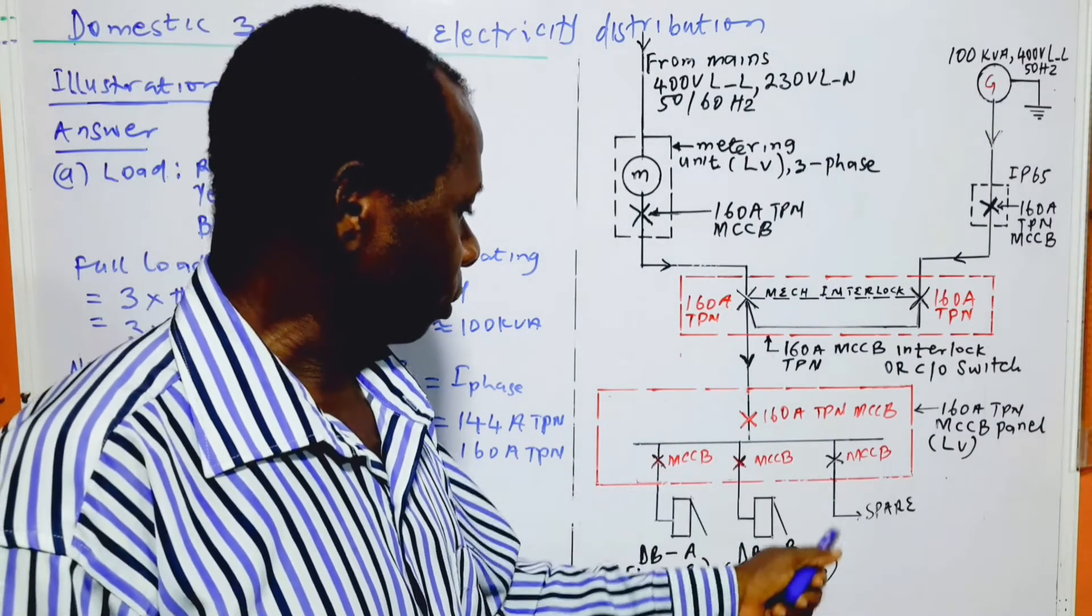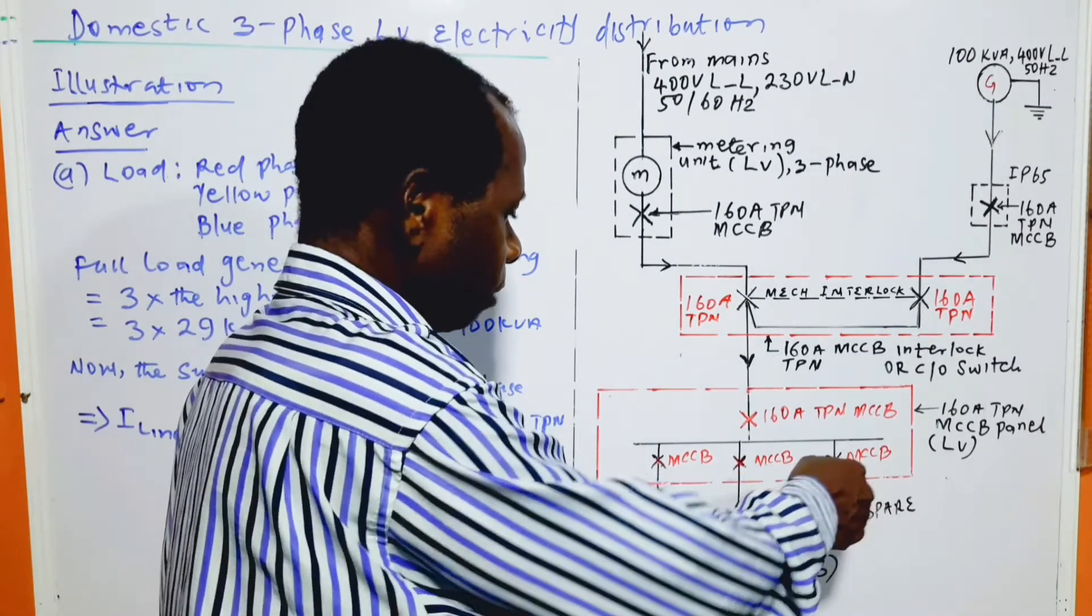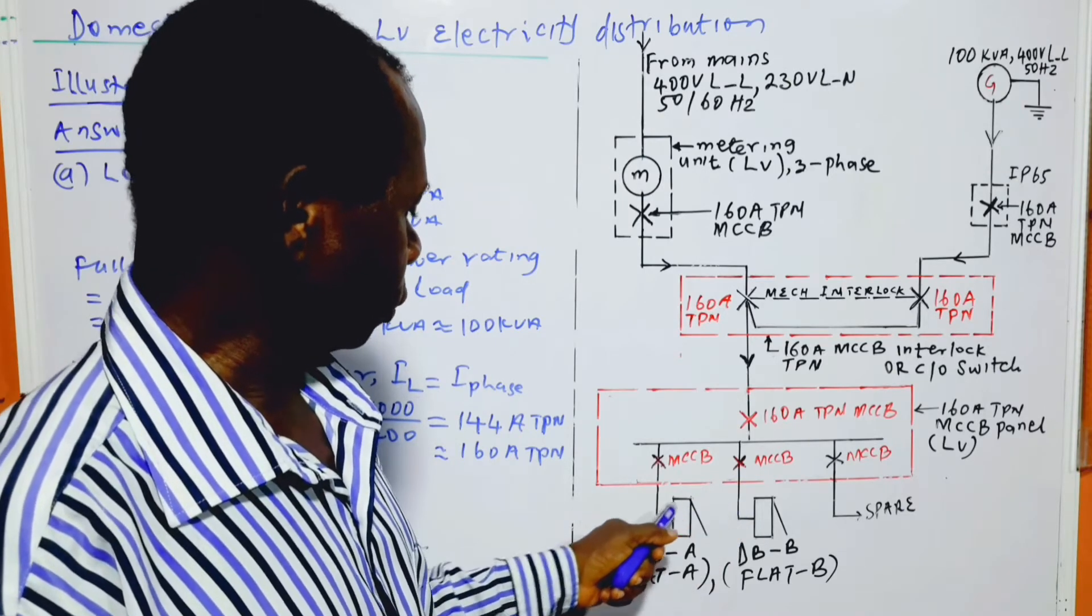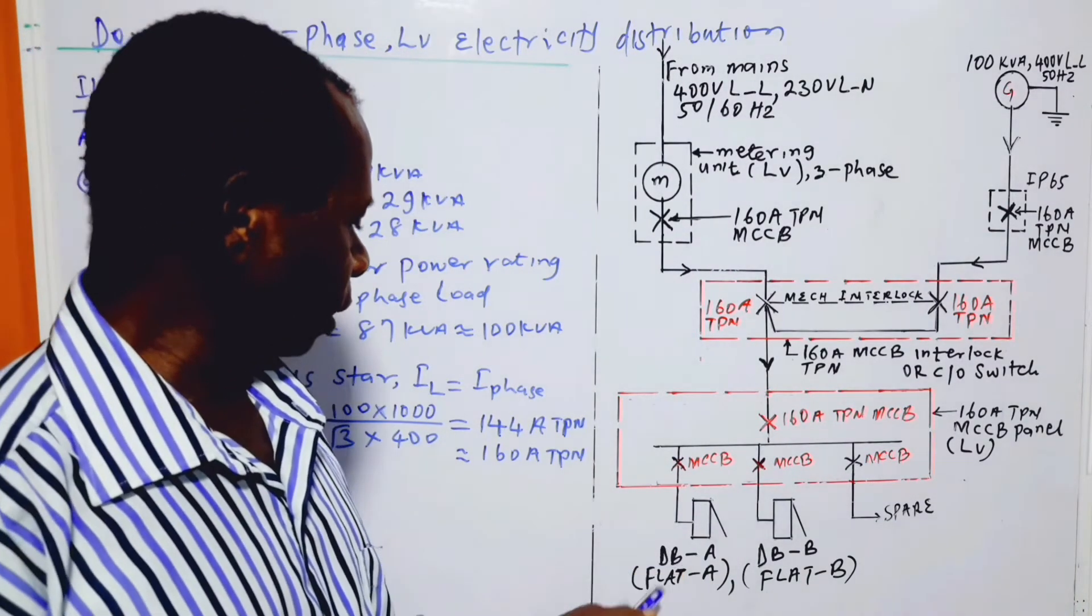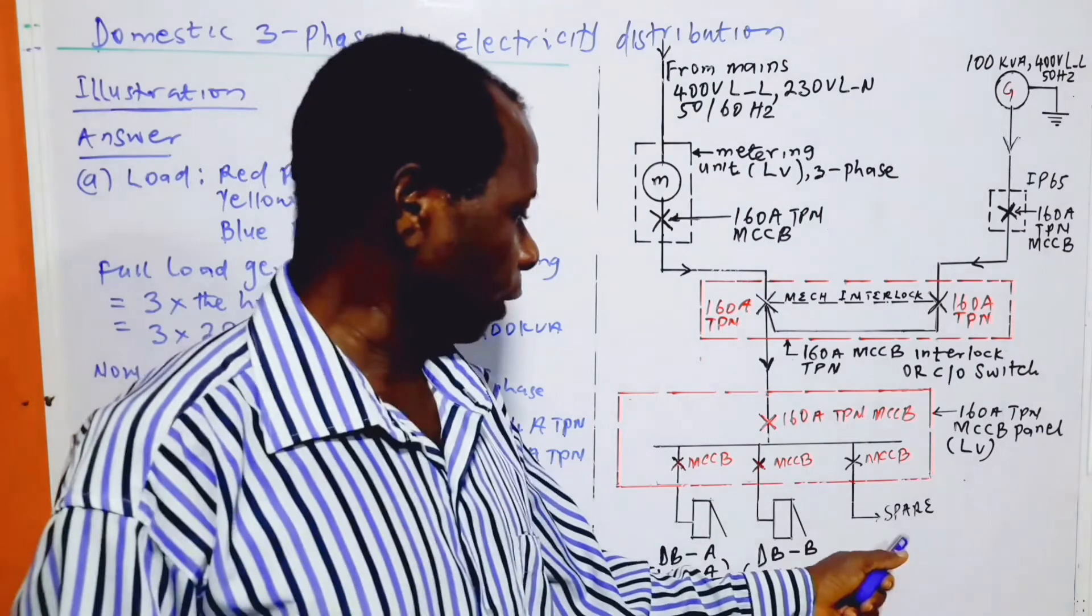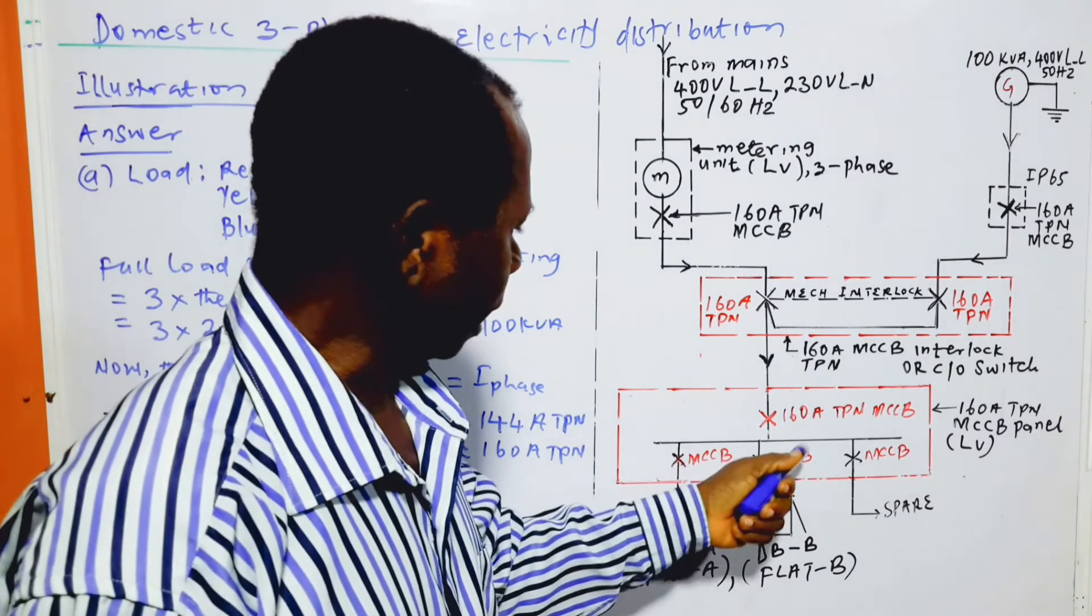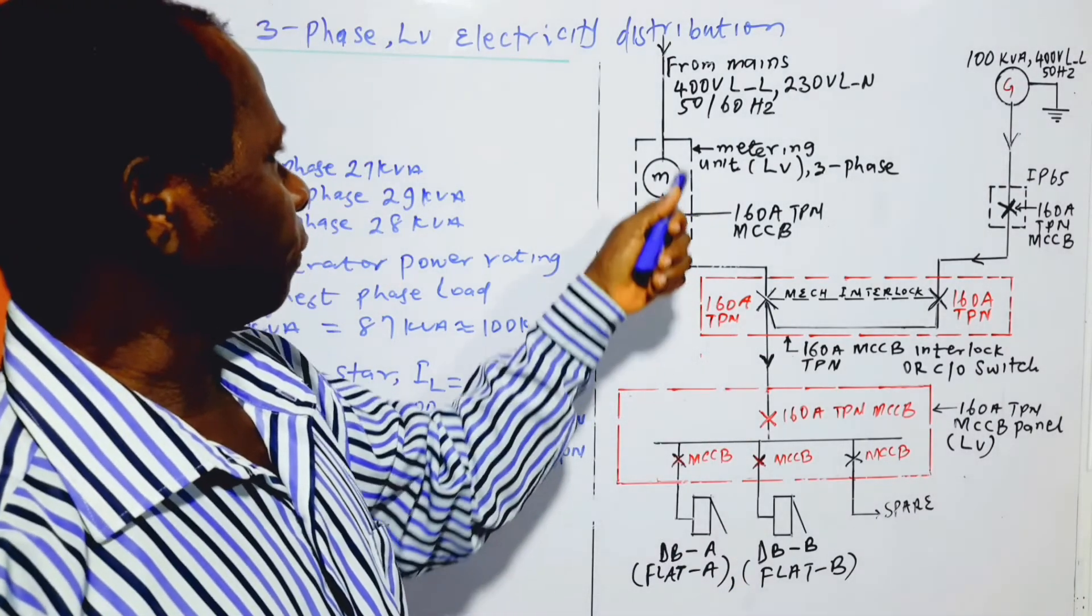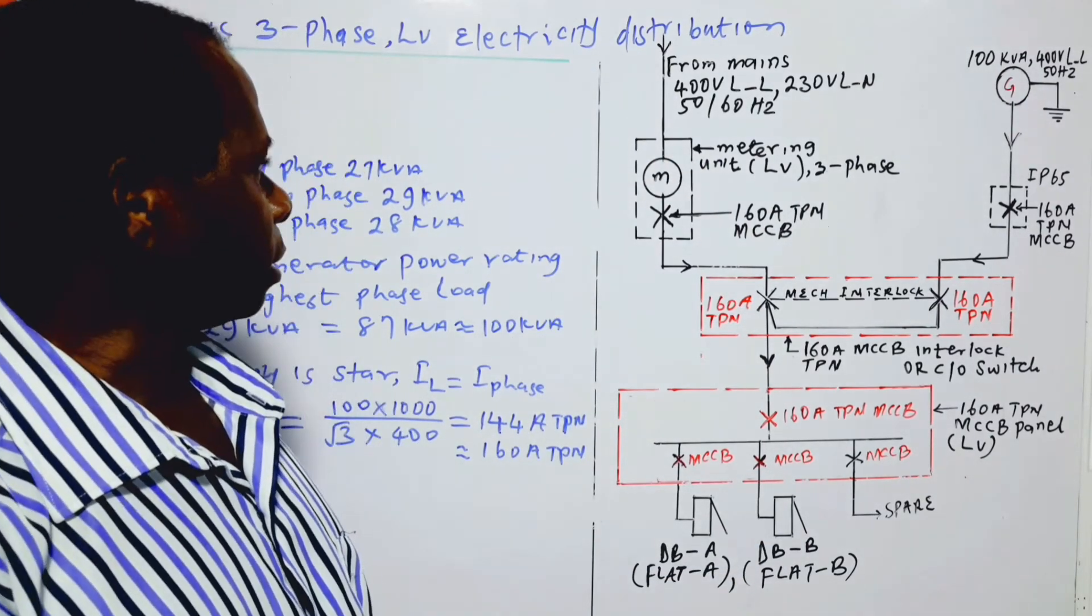These are MCCBs. The sizes or ratings of these MCCBs depends on the ratings of the distribution boards. This is distribution board A feeding flat A, distribution board B feeding flat B, and we have a spare outgoing. The outgoing could be more than three, depending on the number of flats to be reasonably fed with a three-phase low voltage power supply system.